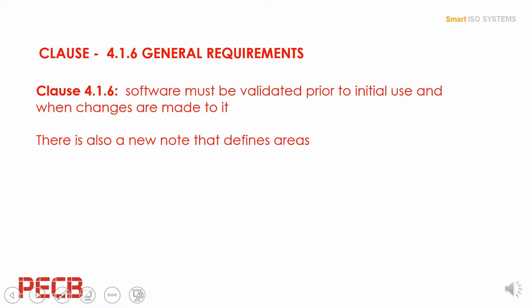Software validation. The standard will require validation of all computer software that is used as part of the quality system. While it has never been a requirement of ISO 13485, software validation has long been discussed in the industry. For example, questions arise like, what if you use an Excel spreadsheet to control a process? Do you have to validate that spreadsheet?